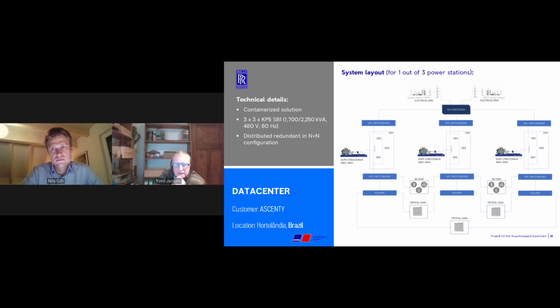At Ascenty Hortolandia, each of the power stations has 3 independent dynamic UPS units, and we can load each dynamic UPS up to 60% of its power rating while still protecting the load with N plus N redundancy. So it's basically the topology of distributed redundancy with totally separated, single and independent dynamic UPS units.